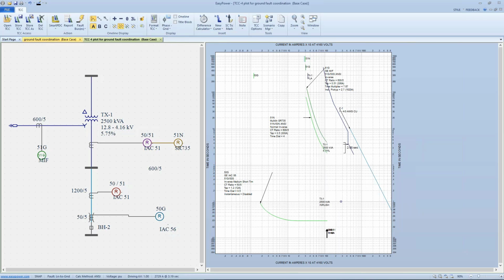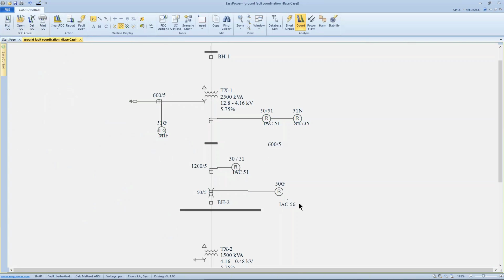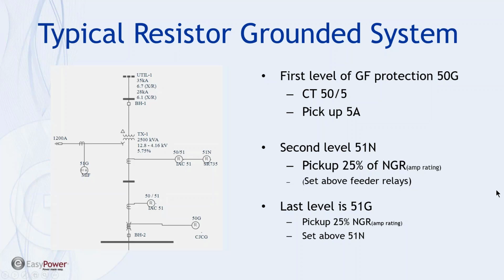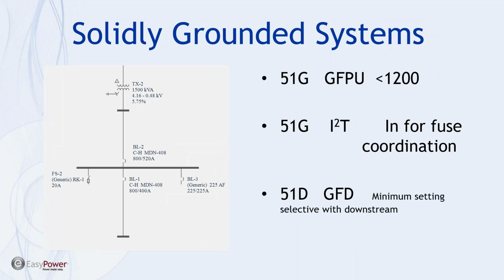All right, so that's a grounded system, high resistance grounding, and it's relatively straightforward. Probably the trickiest part is remembering to apply either a single line to ground or dual line to ground fault as we're doing the coordination. All right, so let's close this and go down to the hard grounded side of the fence. Here it's a little bit different.